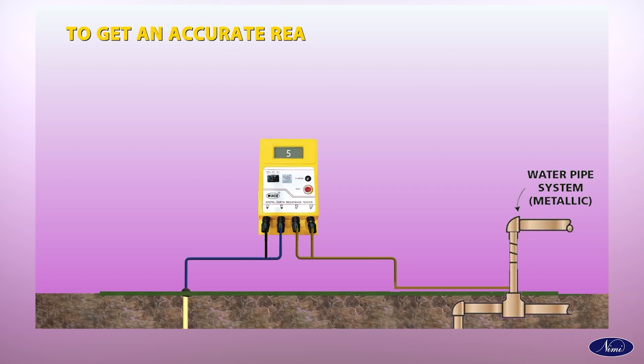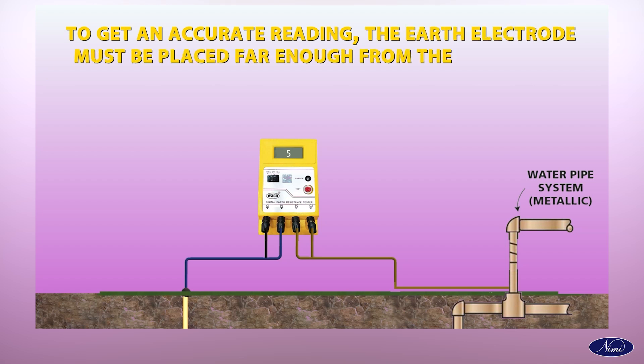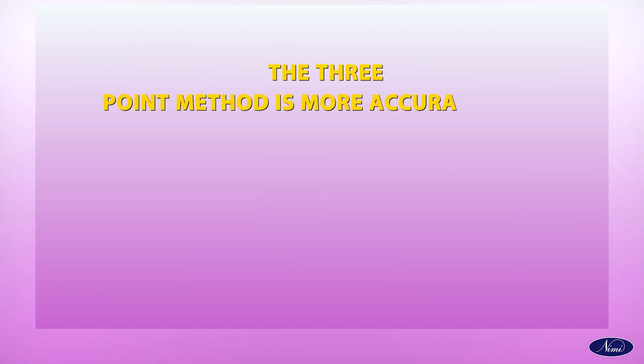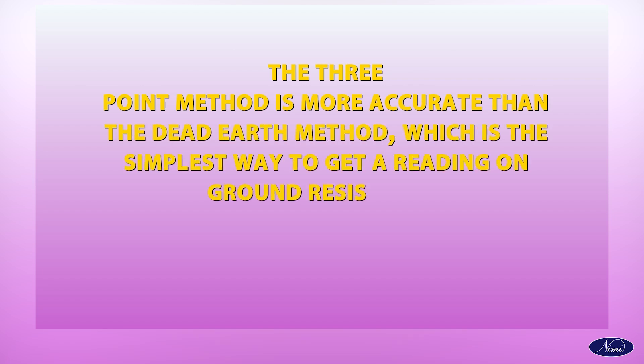To get an accurate reading, the earth electrode must be placed far enough from the second grounding point to be outside of its field of influence. The three-point method is more accurate than the dead-earth method, which is the simplest way to get a reading on ground resistance.